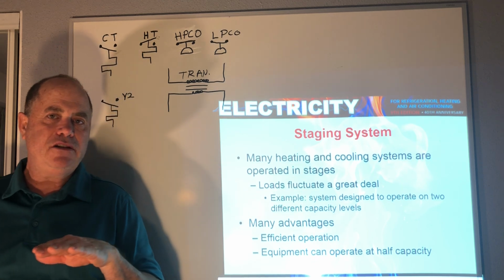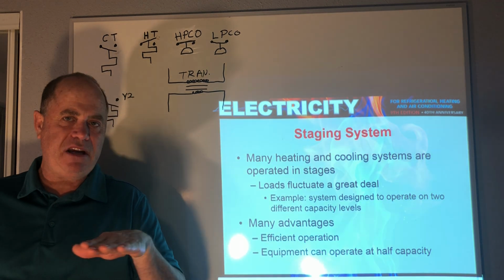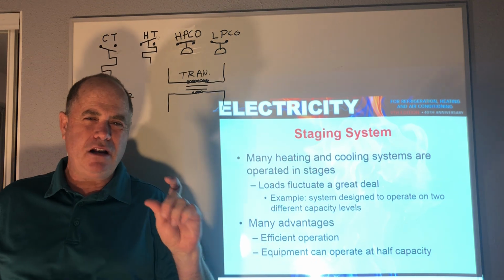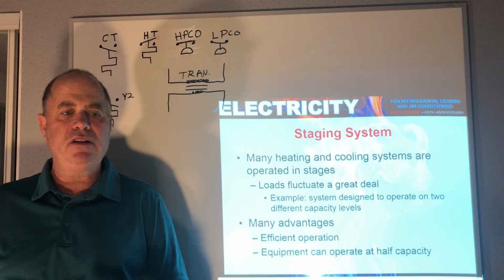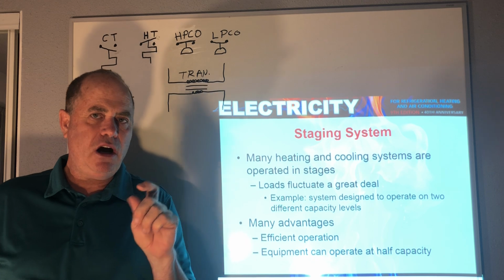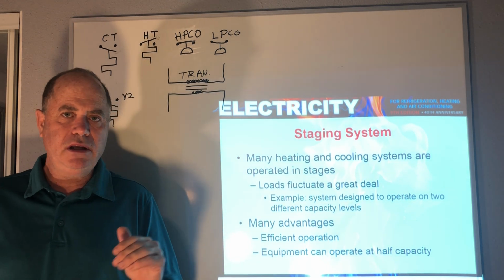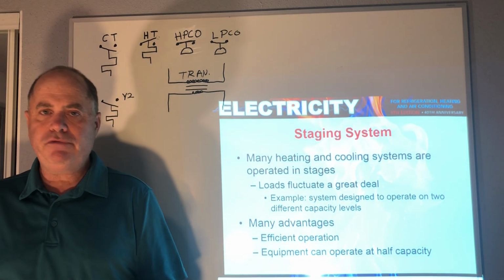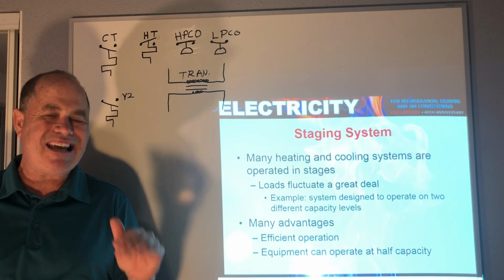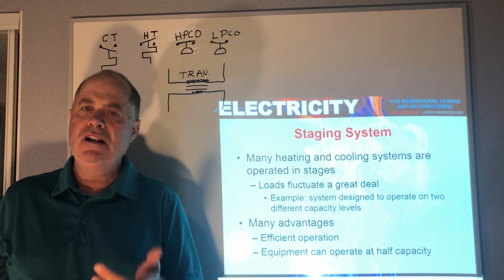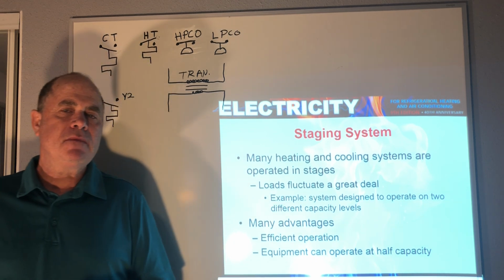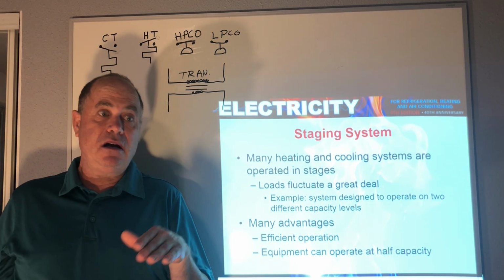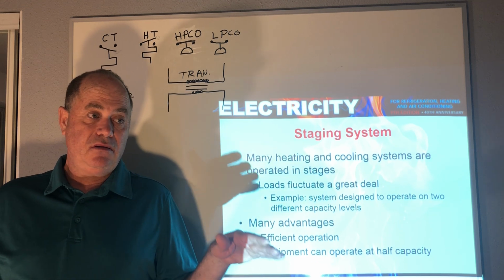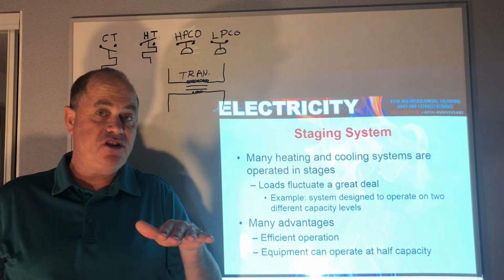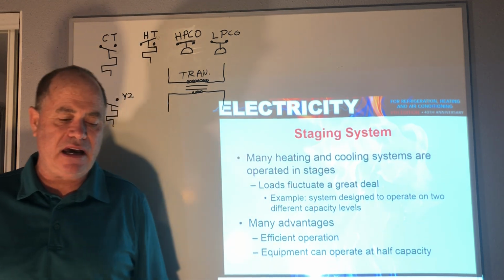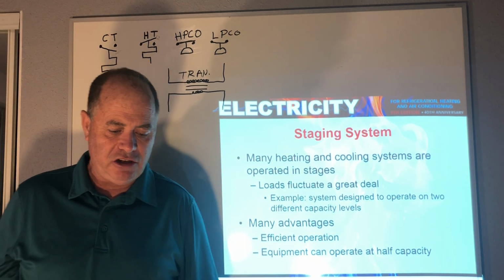It's nice to allow the equipment maybe to be run at a little bit lower pace for longer periods of time. That'll also maintain a more even temperature instead of a simple thermostat with one set of contacts bringing on the cooling at 74 and shutting it off really at 72. I know that your thermostat is set at 73, but that's really what's happening for a simple system in a house. It might be more like it comes on at 70, it's running more just at 73 and a half and maintaining that with modern technology.